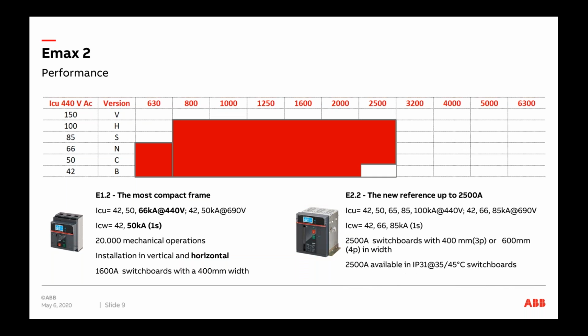Then the E2.2, which is our 2500 amp breaker, we can go all the way up to 100 kA and can fit onto a 400 mil wide switchboard. Now, having said that, that's quite a compact design. Now, there are certain other parameters that need to be looked at when we are trying to fit a large breaker in that, and that will be based on temperature rise calculations as we do as standard.